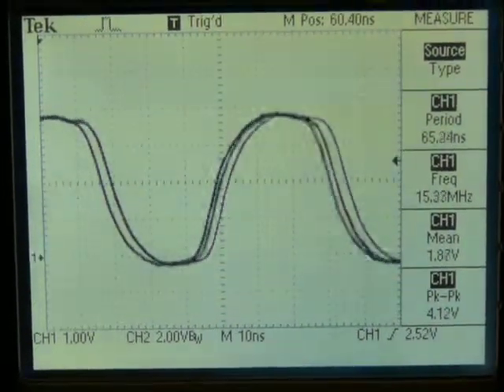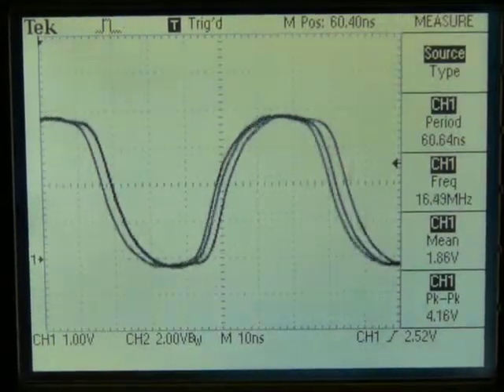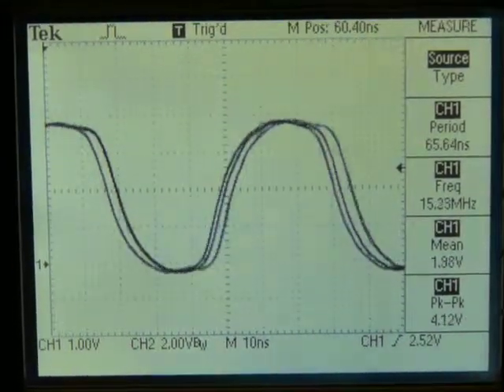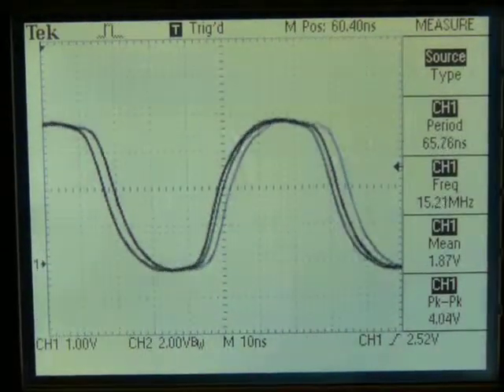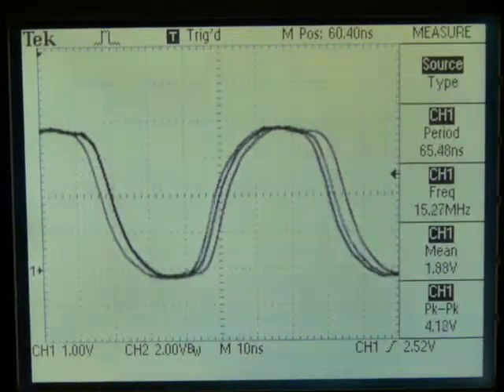So with the factory calibration, you never know what value the modulator is going to have. It most likely will be in use because there's only one of 32 values that will disable the modulator.